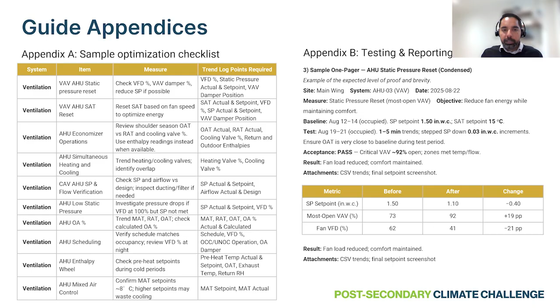As a result, the fan VFD dropped from 62% to 41%. So that's the change that happened as a result of implementation of this. With this list and this testing report, you can combine them and use them on a periodical basis. Set those time requirements with your controls contractor, or with your internal team if they have a tech who could do all of these, and have them report, so that you have a standard process set up as a regular PM to look at the energy as well.